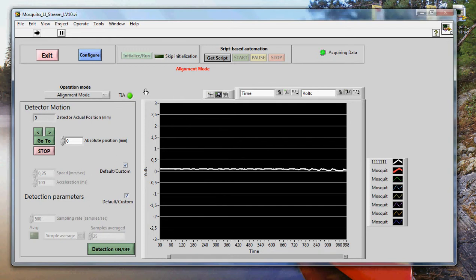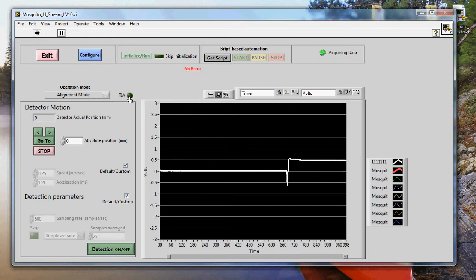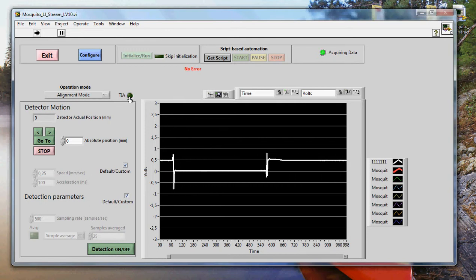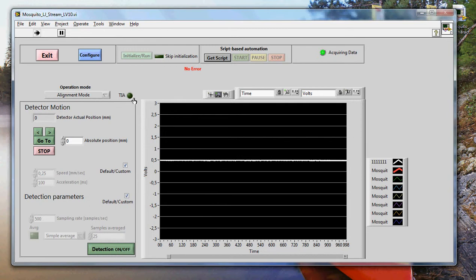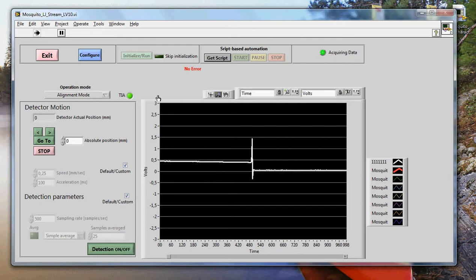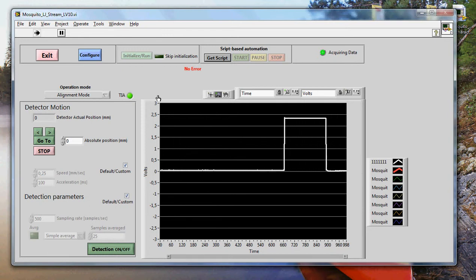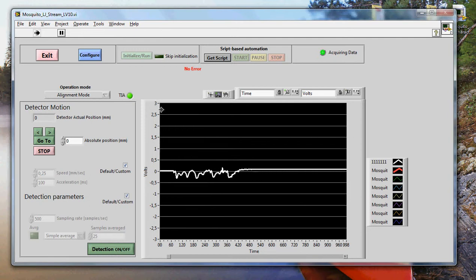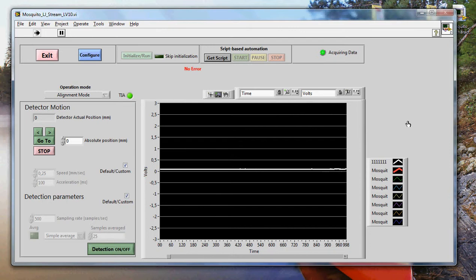This is the button on the mosquito box. This is the voltage to the detector. On and off. You can see here that we're turning now the bias current off. So basically, if I move the fiber, the signal is dead. We're not measuring anything. So this should be on. And the button from the mosquito box should also be on. And now you have a live signal. Just move the delivery fiber. And because it's damaged, you will see some signal. Or just move the transducer. And it will also give you a signal.